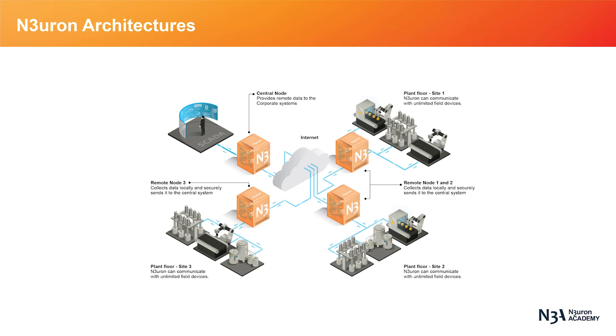Neuron nodes communicate and exchange data between each other via links. Neuron links allow data to flow continuously between nodes, visualizing real-time and historical values or alarms in the source and destination node. Once connections have been established, they become fully bi-directional. This allows all data sent to be encrypted using Transport Layer Security (TLS) protocols to prevent any data tampering.